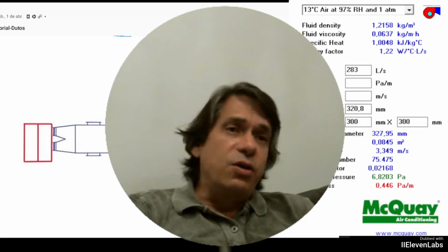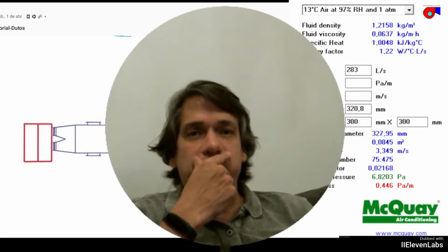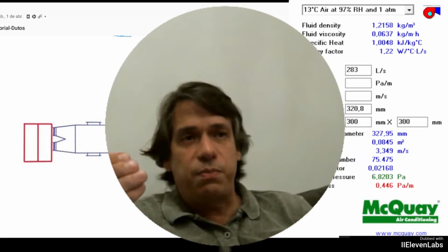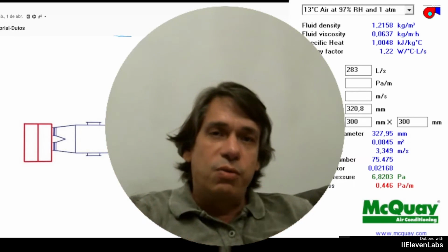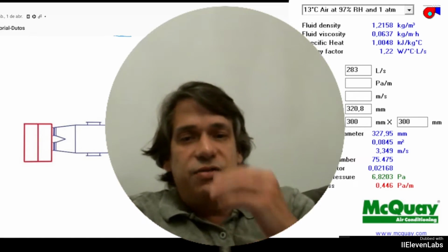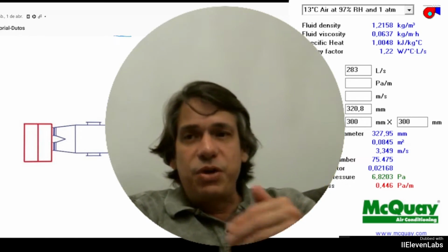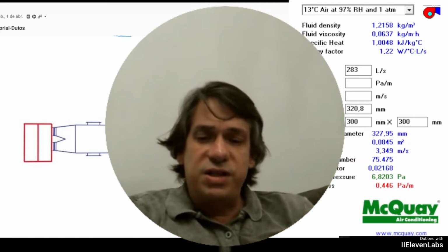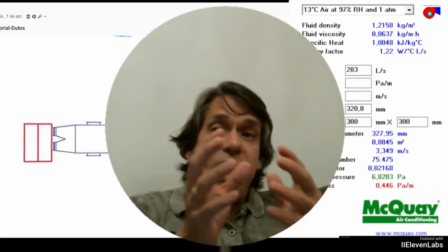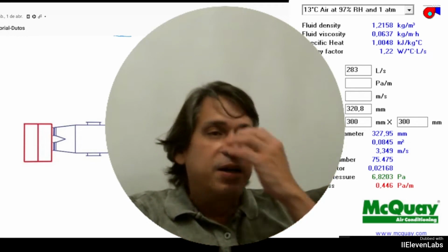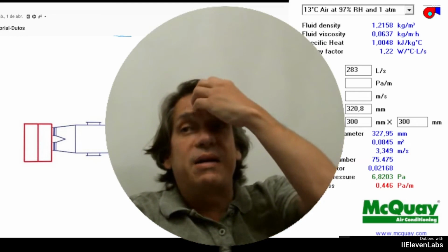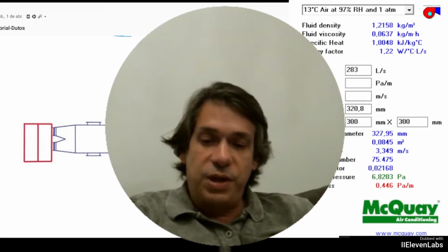The third method is the static pressure recovery method, a slightly more complicated one that involves complex computations. Most of the time, due to its calculation complexity, it is not used. It is used in very specific systems, although it is the method that gives the best balance of the duct network, okay?